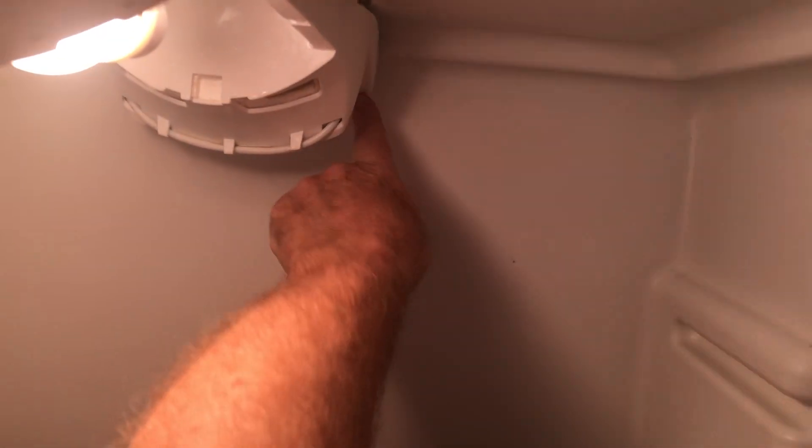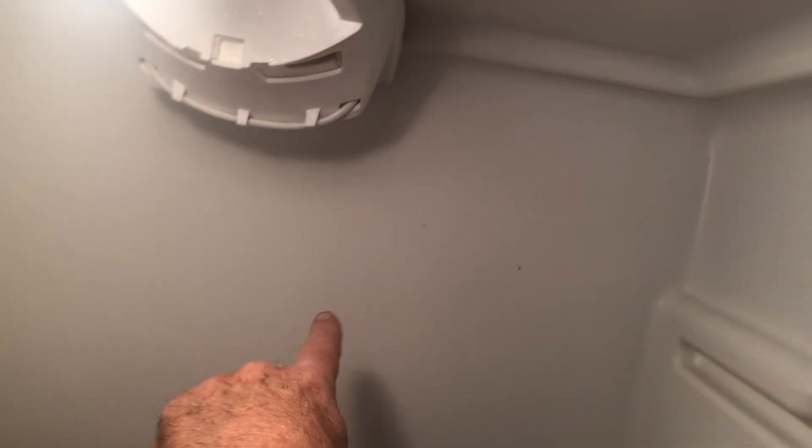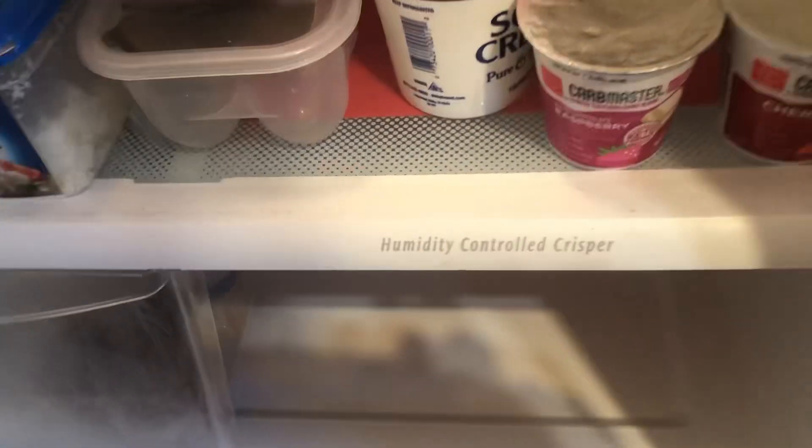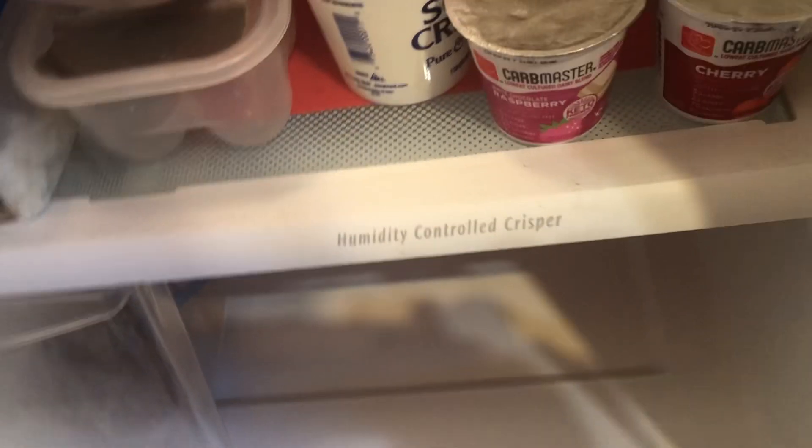The water actually drains back here behind in this little pan that's located right back here, and sometimes when it stops up it will go right down the bottom of the unit and you'll find water gathering here in the bottom.